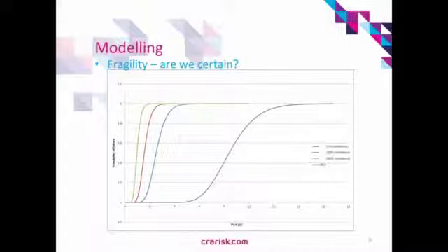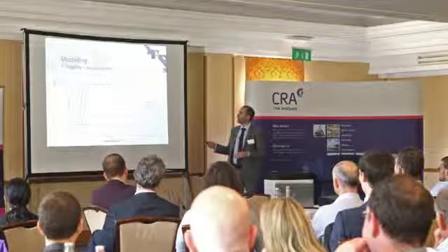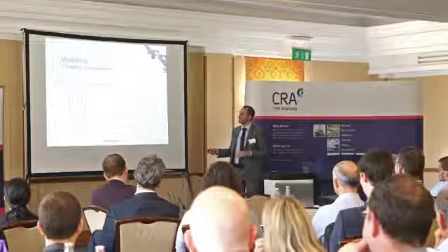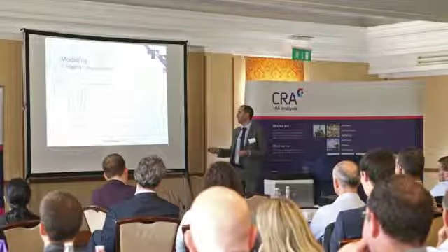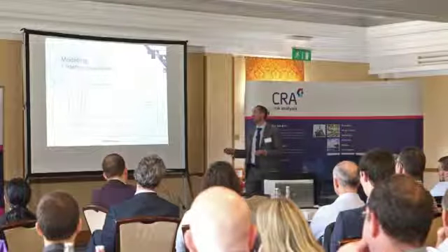So it's quite extreme over to the right. To give you a rough idea, what we're looking at here is probability, which goes from 1 to 0. Because it's not logarithmic, as soon as you see a little bit of lift off, it means you're going to see some quite high probability of failures. On the red one, you're seeing around about 1g. The JNES for the same component isn't lifting off until around about 5. That's a massive difference, especially when you're talking about peak ground acceleration in terms of g.